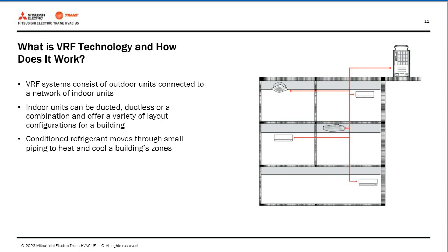VRF systems heat and cool zones by moving refrigerant through small diameter piping, rather than traditional VAV where you're moving large volumes of air in larger ductwork. During the colder months, these systems draw heat from the refrigerant in heating mode, and in the hot months, these systems reject heat into the refrigerant when in cooling mode. The graphic here depicts an air source system, which is a similar visual to a water source, which we use at the credit union.